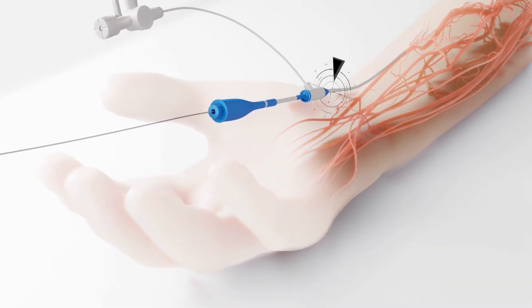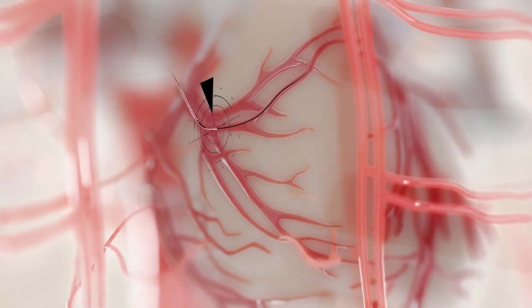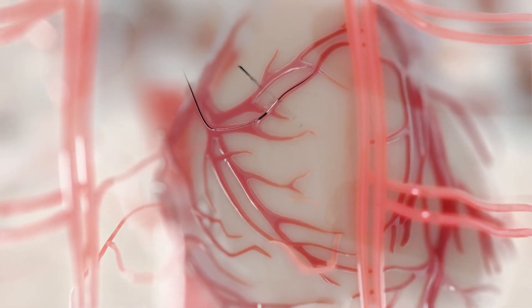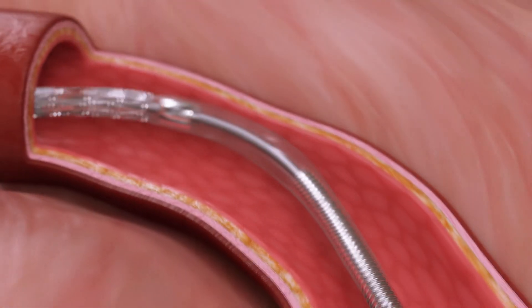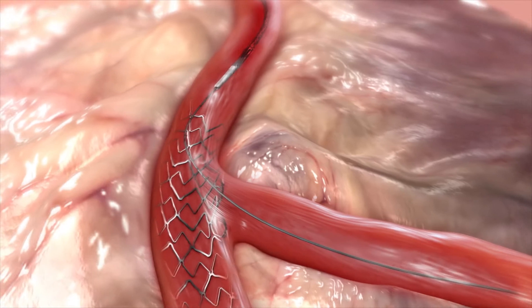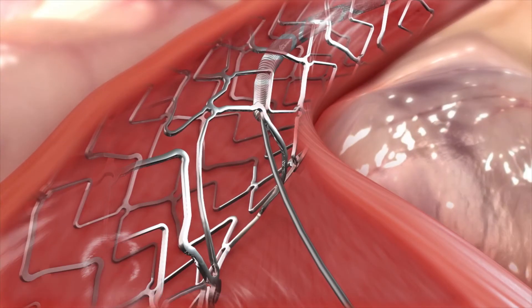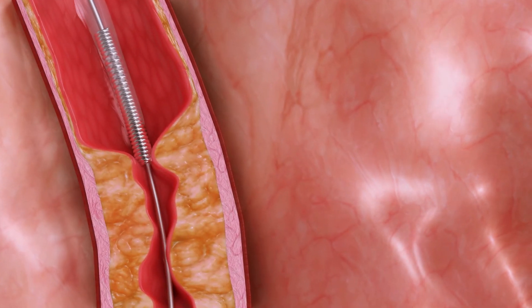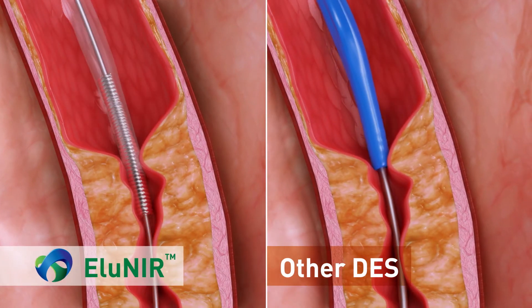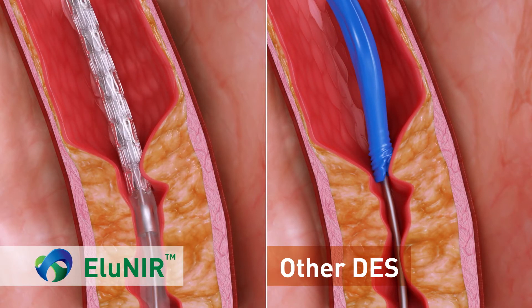EluNIR redefines deliverability with a unique catheter system designed with complex anatomy in mind. A metallic spring at the tip of the catheter provides simultaneously visibility under x-ray, a high degree of flexibility and pushability, and leads the system through tortuous arteries, calcified lesions, and implanted stents. The spring tip closely tracks the guide wire while avoiding fish mouth and buckling, common to plastic tips of other stent systems.